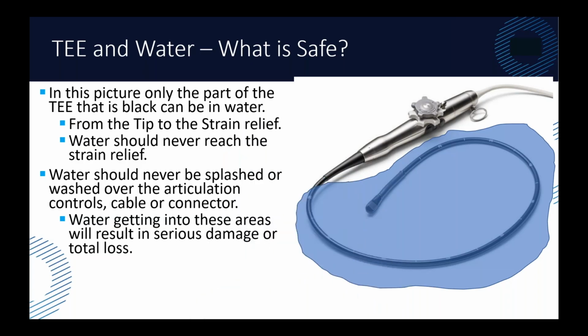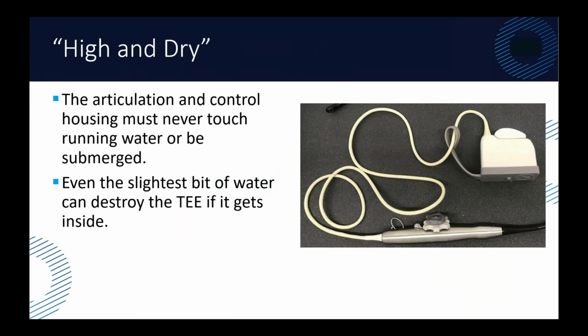But one of the biggest things that occurs is water infiltration. And again, I don't mean to beat up on these folks, but this is probably going to be central processing. It could happen in other areas, but that's probably where it's going to be. This is the part of the TEE probe that should be submerged in water when it's being cleaned. The other part of the TEE probe should never even be splashed on. So we call it the high and dry section. The only time water should hit it is on a cloth.